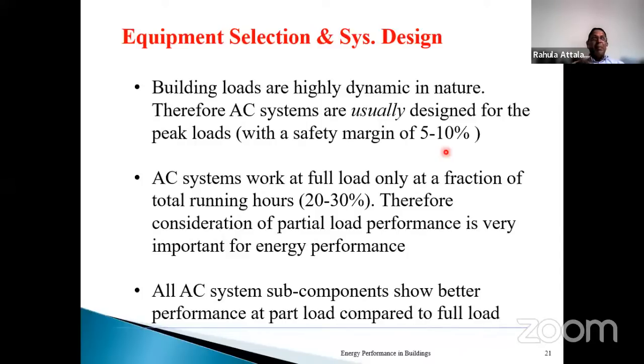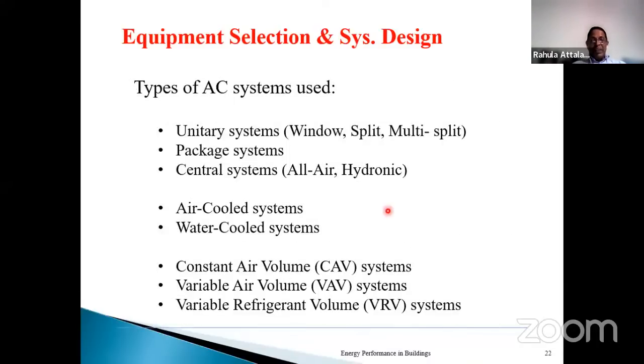So one might think, why do you need to oversize? Because you might be spending unnecessary initial investment. True enough, by slightly oversizing, you pay additional investment initially. But since it operates efficiently, and the operational period is quite longer and the operational cost is quite higher than the initial cost, it's not a bad idea to get the part load performance and allow the equipment to operate at a better efficiency. So all this will apply when you come to the equipment selection.